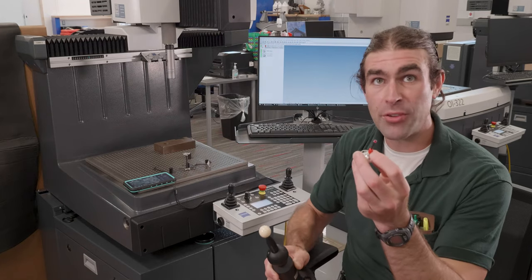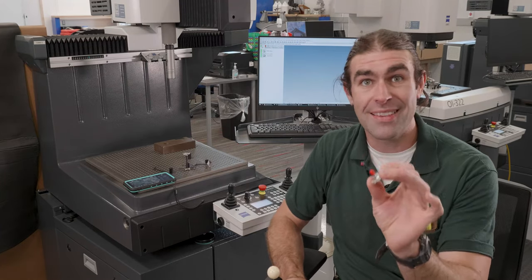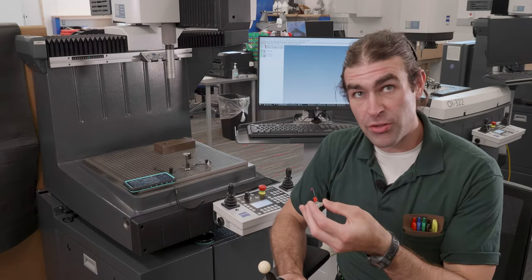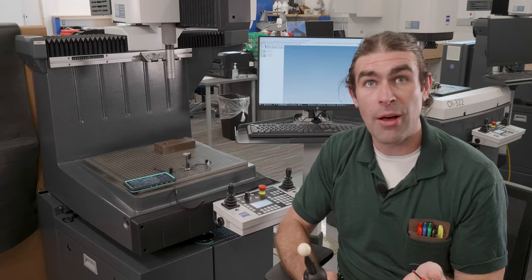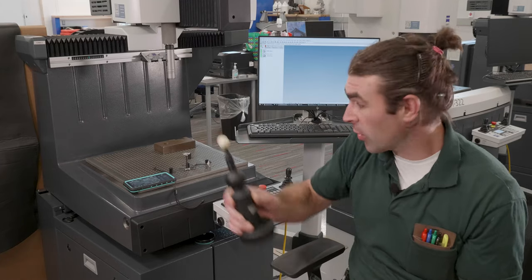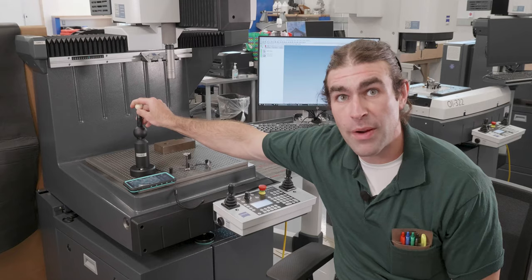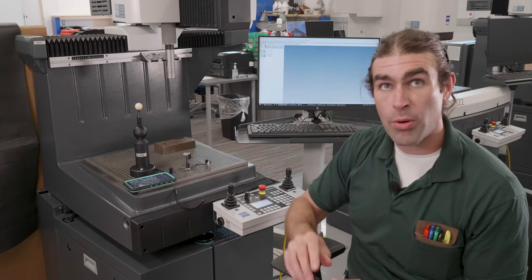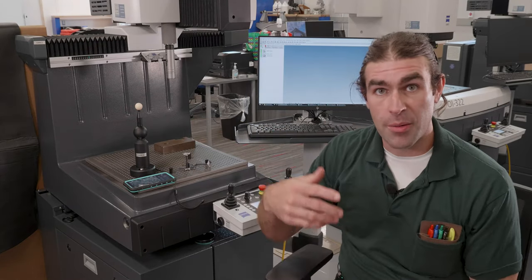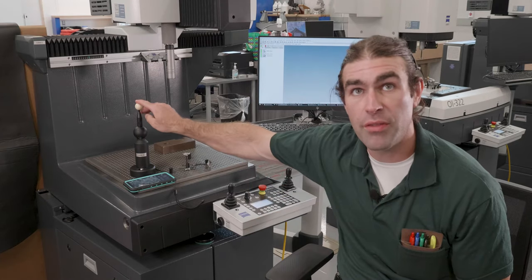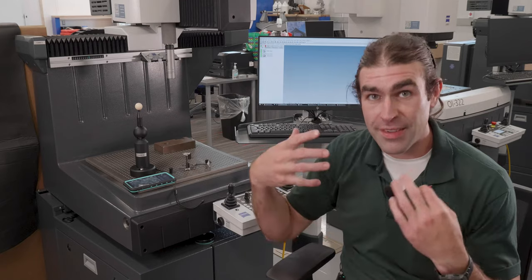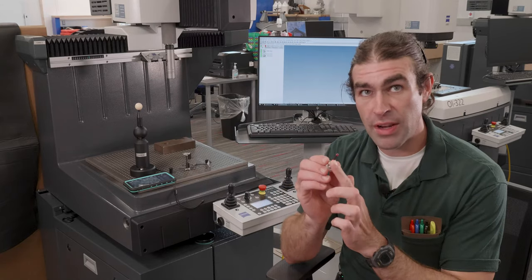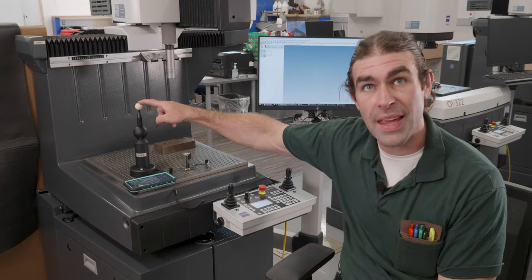Now the master probe is just a probe with a known size and length that comes with the machine that works with this to figure out all the other styli. So the way it works, I'll attach this reference sphere. I'm going to run a program with the master probe which will get the position of the reference sphere. So it's going to establish a zero. It knows everything about this. It'll know everything about that.